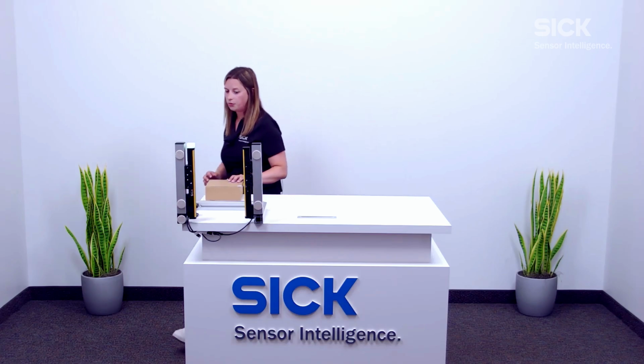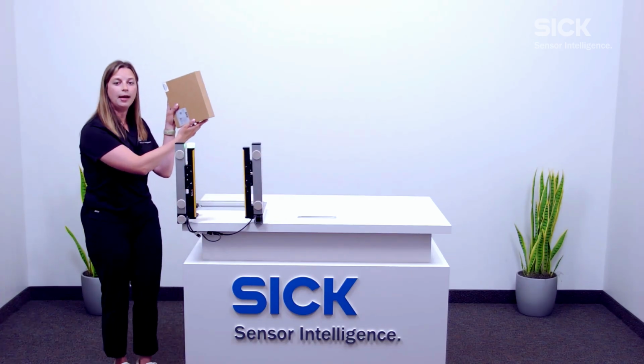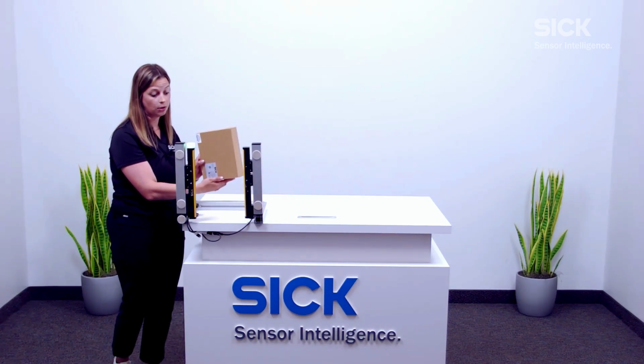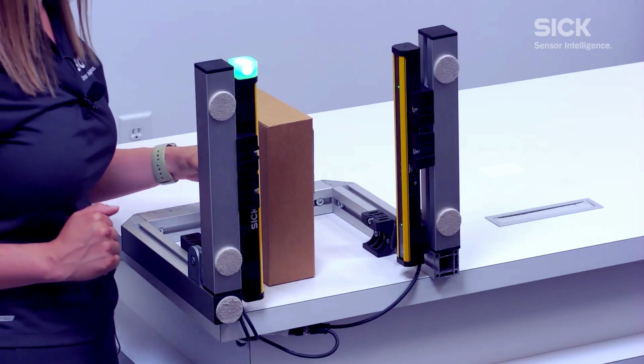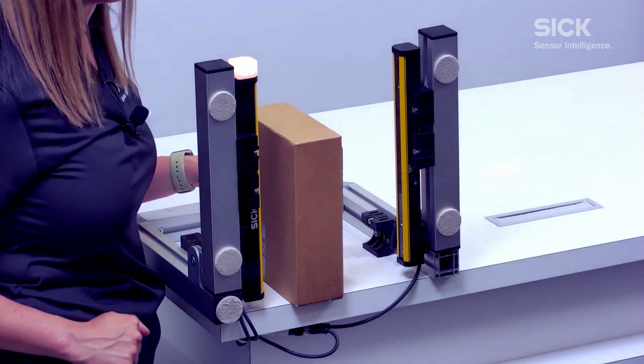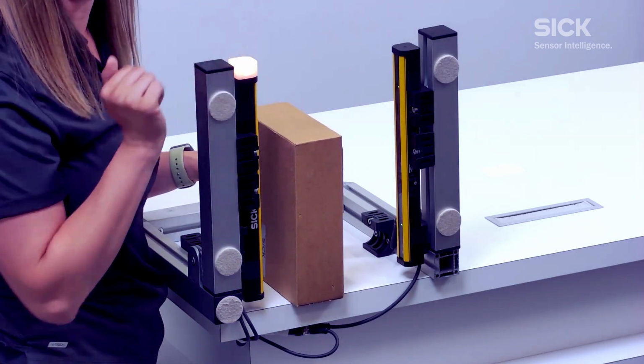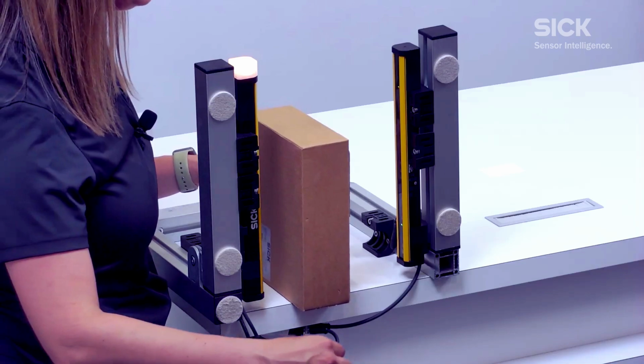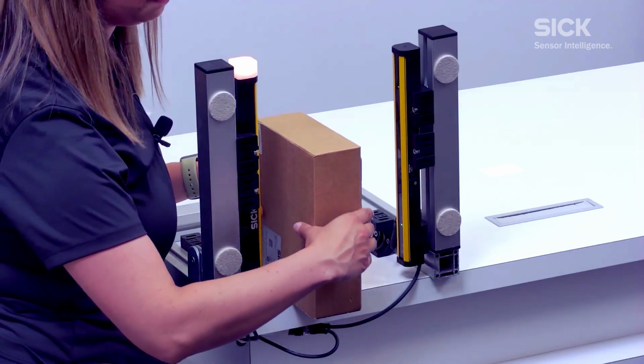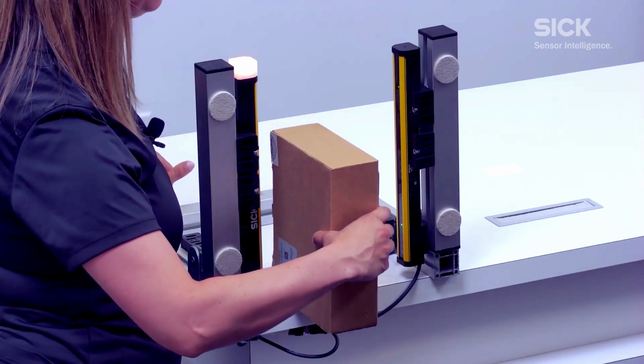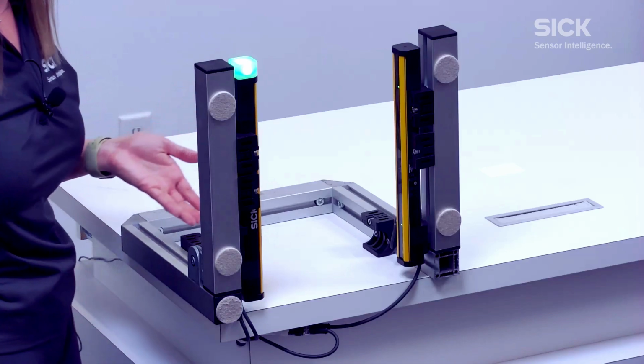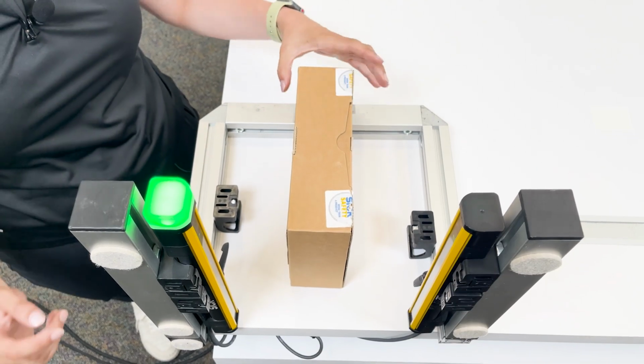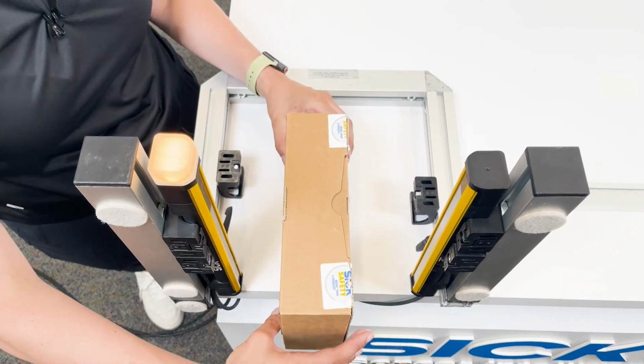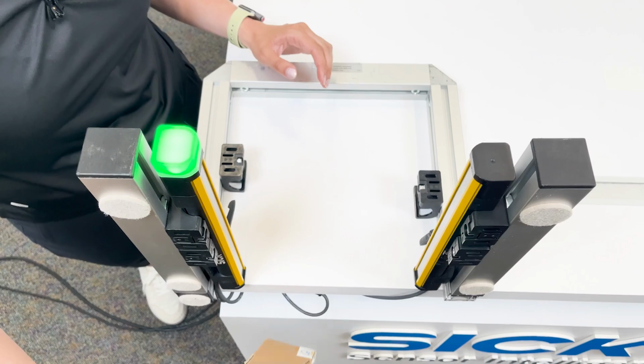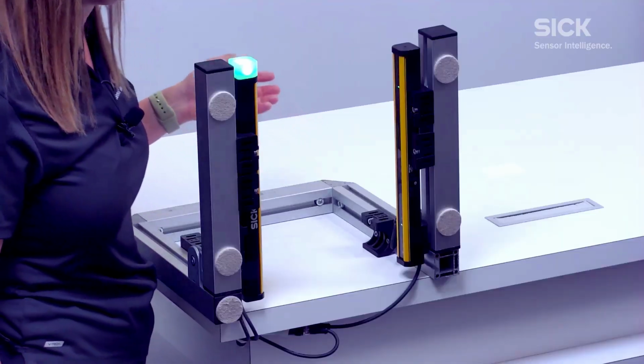Here I'll walk you through how it works. Here I have a box with a rectangular contour. I'm going to feed it through our safety light curtain. You'll notice that the end cap goes yellow, so it's in a state allowing smart box detection to be active. Once it's clear, the light curtain goes green. Throughout that entire process, our safety signal remains high, which means the machine is still able to operate.